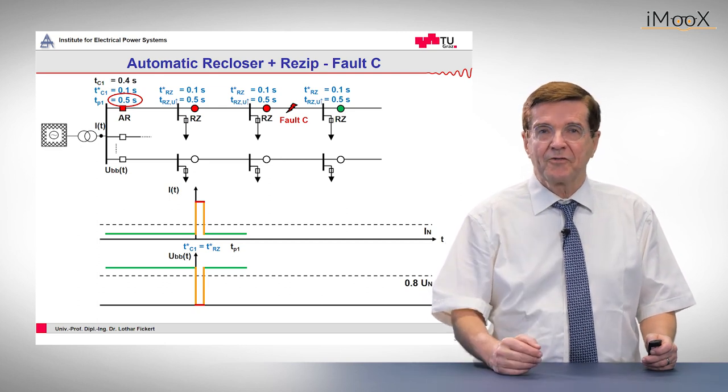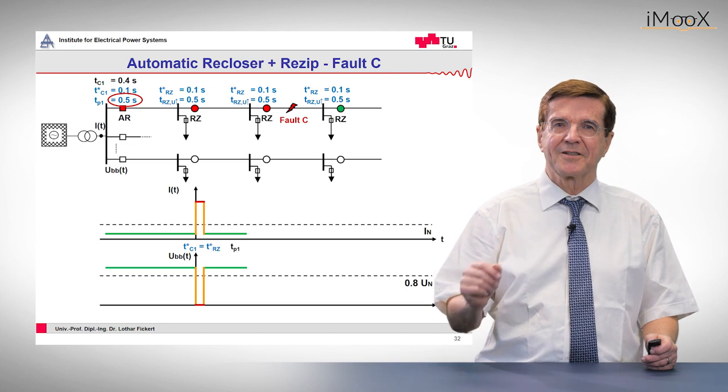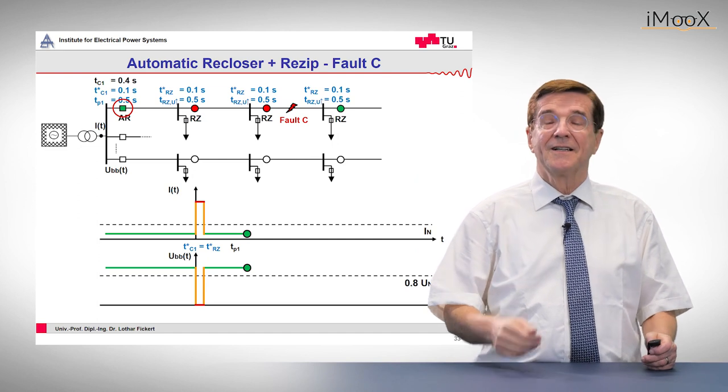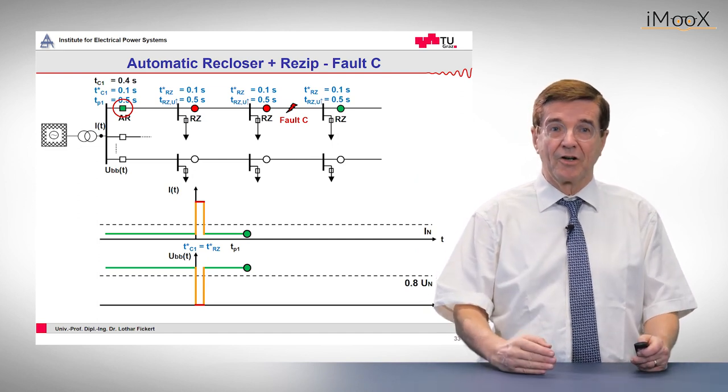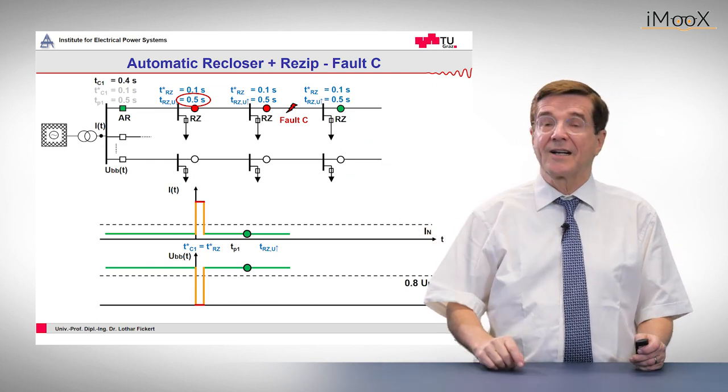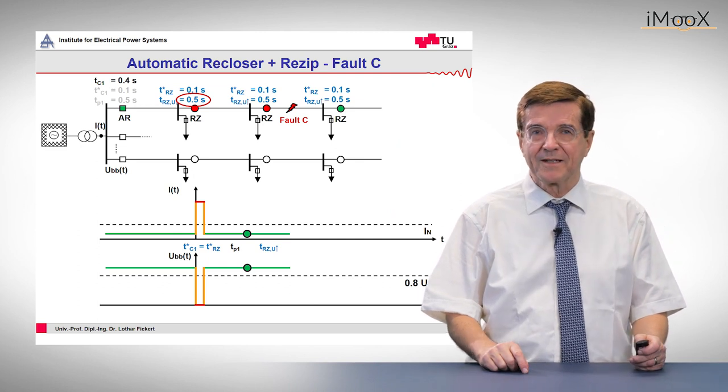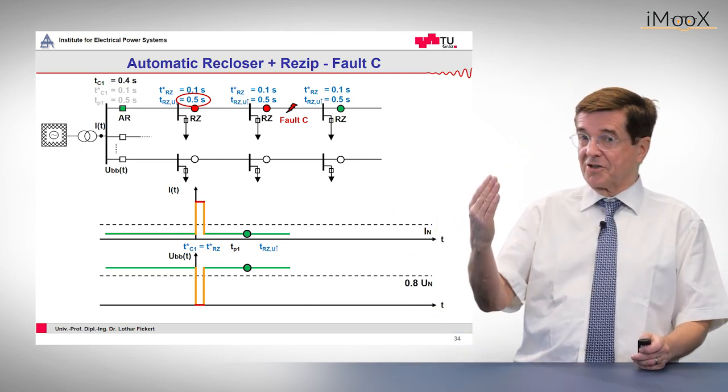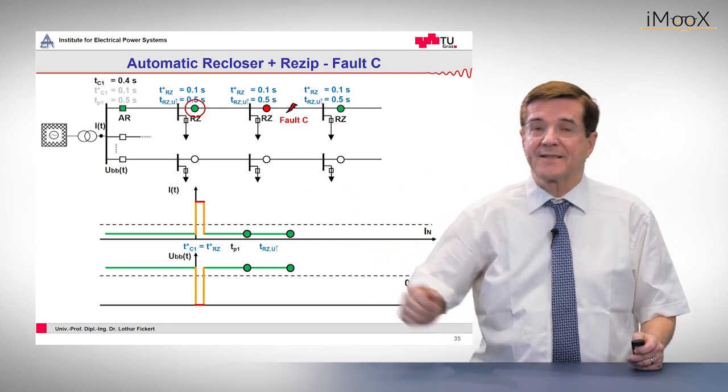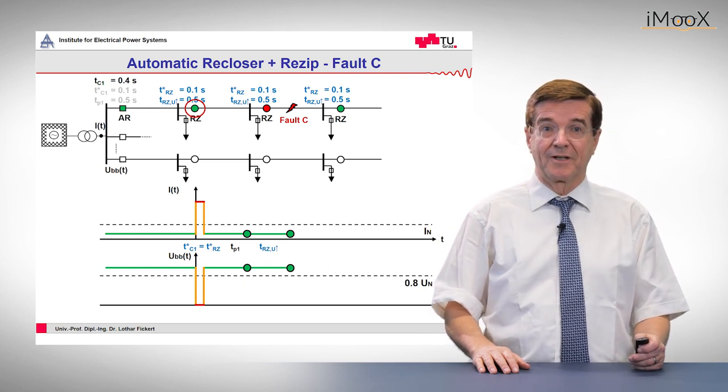Now after 0.4 seconds, an automatic switching sequence starts. We start at the beginning of the line, where after 0.5 seconds this auto recloser relay closes and energizes the line, including the next bar and the next re-zip auto recloser. So what happens here? The auto recloser sees a voltage coming, waits half a second and closes, and passes the voltage on to the next busbar and the next re-zip auto recloser.